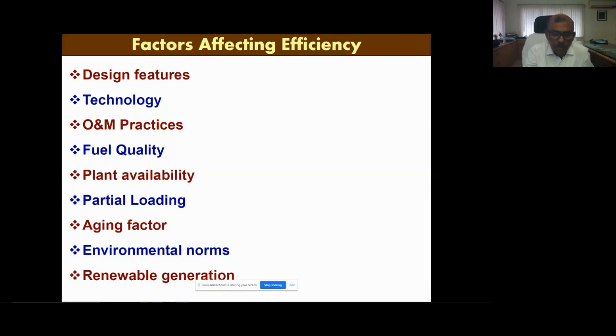Then the O&M practices. The O&M practices adopted by any utility or power station have a major role in the overall efficiency parameter of a unit or a power station. So that we'll discuss and deliberate later on. And apart from that, as we all know, boiler performance is very much dependent on fuel quality. In our case, fuel quality is low grade lignite, having GCV of 2500 to a maximum of 3000, but more generally we get around 2800. And moisture content is the main limiting factor, around 43 to 52%. Now it is mostly in the 50% range, 50 plus.